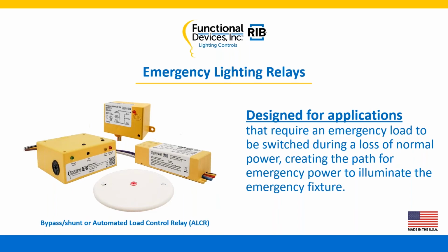Some models include contact ratings from 5 amp to 20 amp max. Some include 16 amp electronic ballast ratings for those LED applications. Many of the ALCRs have the ability to override 0 through 10 volt dimming applications. Our most recent model, which we'll show you here in a bit, will give you the 0 through 10 volt dimming, and it'll give you the offer to DALI dimmable override capabilities, something new to us. And lastly, some of our models offer both fire alarm system input and remote test capabilities.